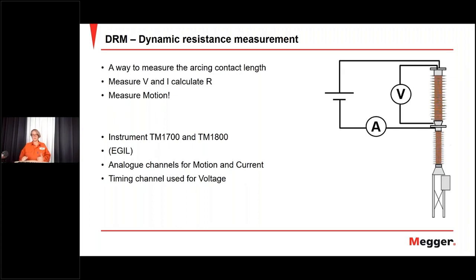But DRM measures the arcing contact length to know, without taking apart the whole circuit breaker, how much life length you have left of the arcing contact. How do you do it? Yeah, it's a little bit like the static resistance measurement, almost like contact resistance measurement, but you're doing it during an operation. So you measure voltage, current, and calculate resistance, and measure motion at the same time.